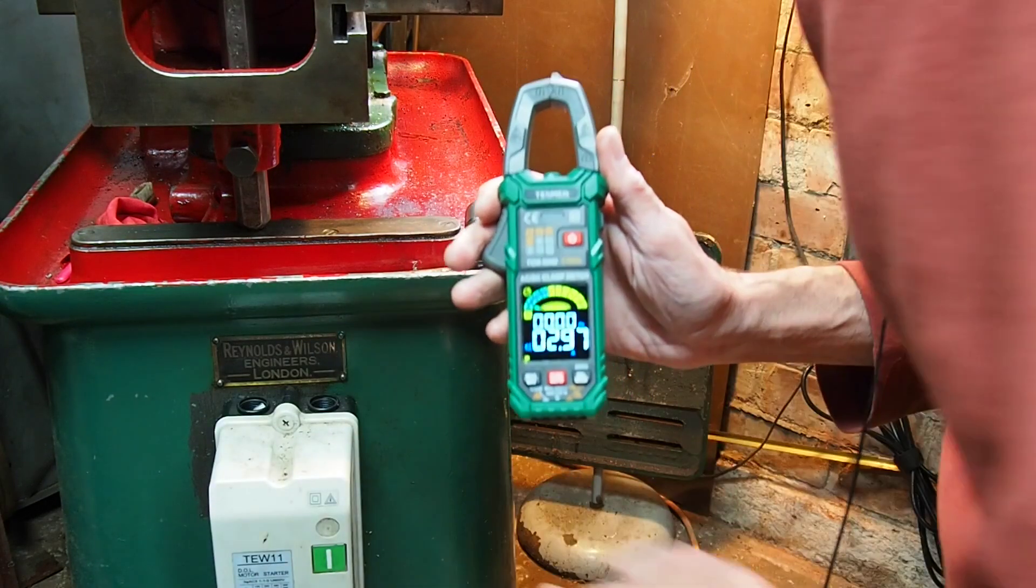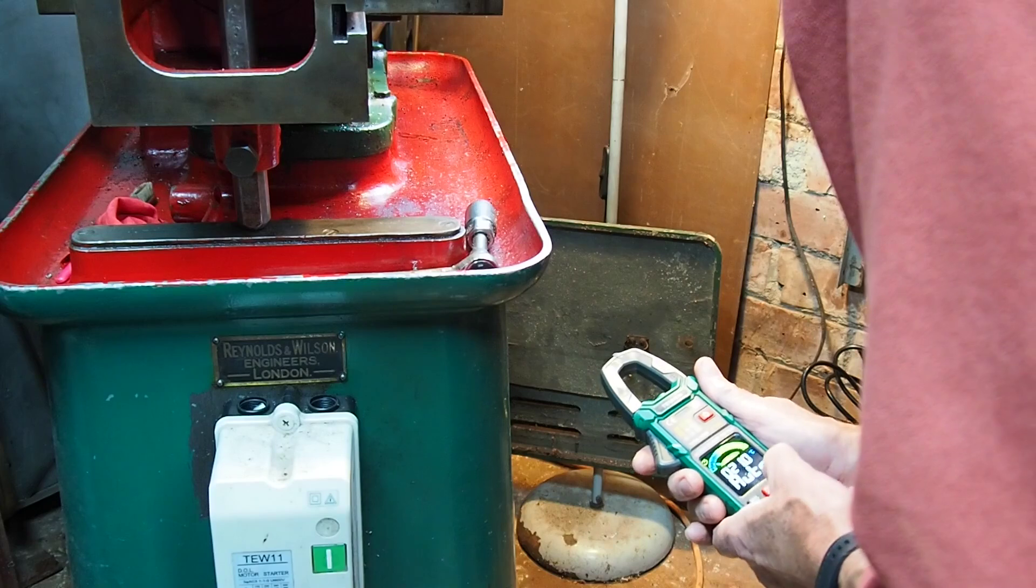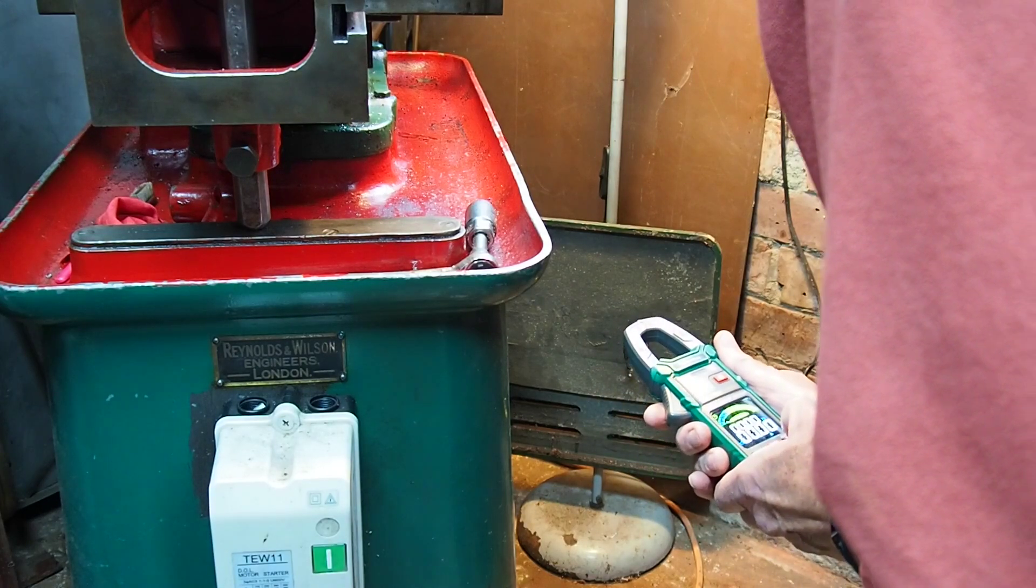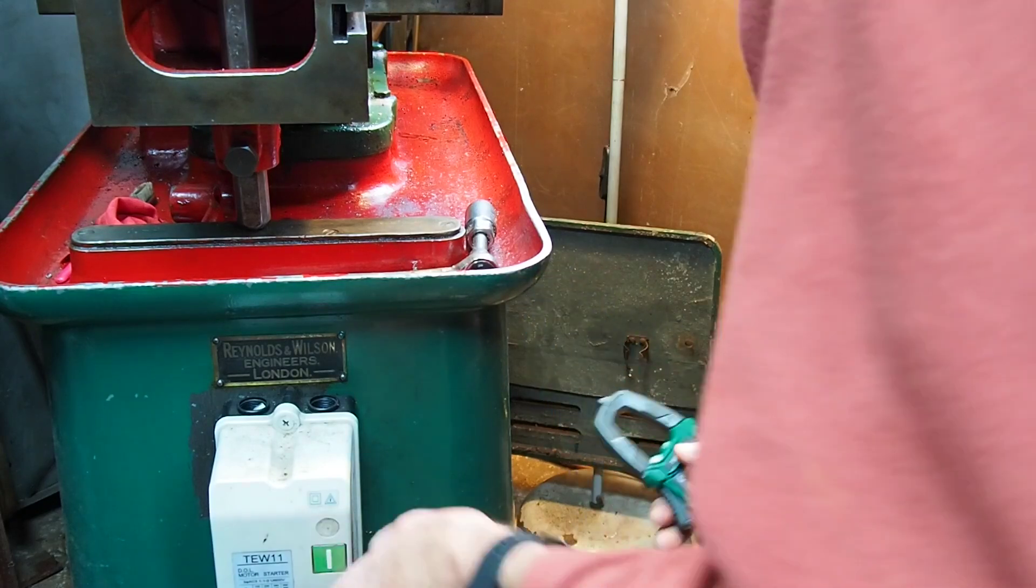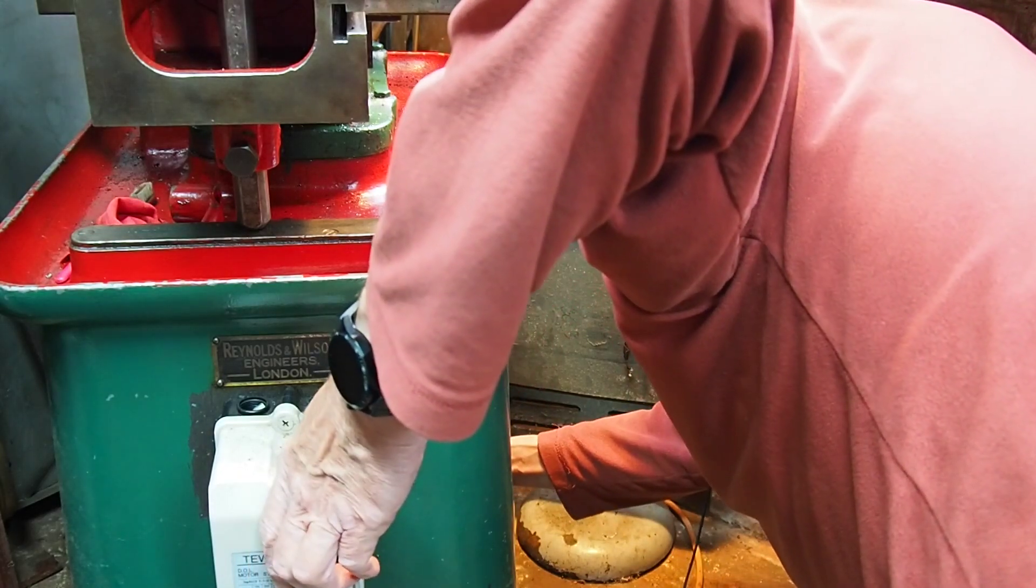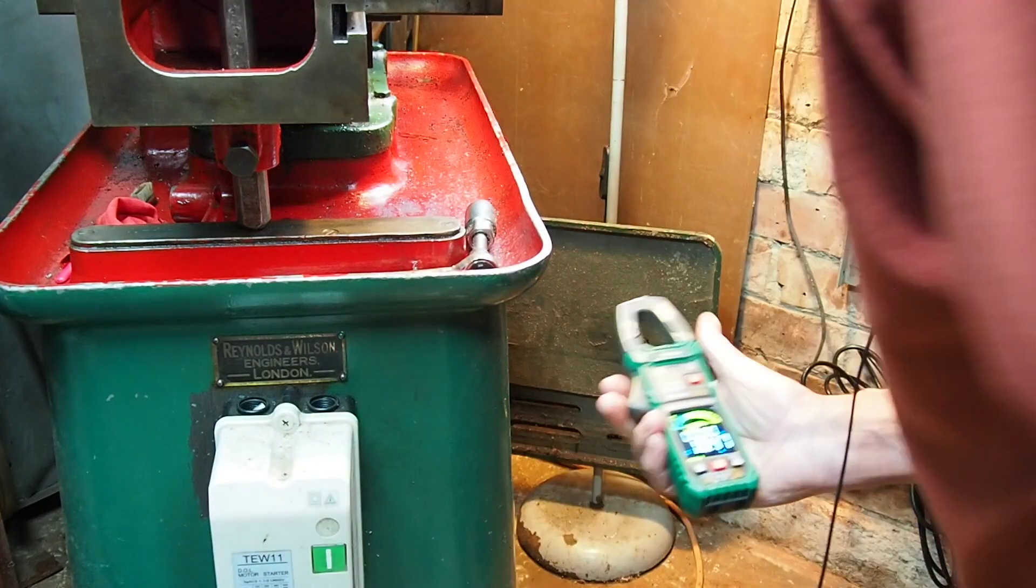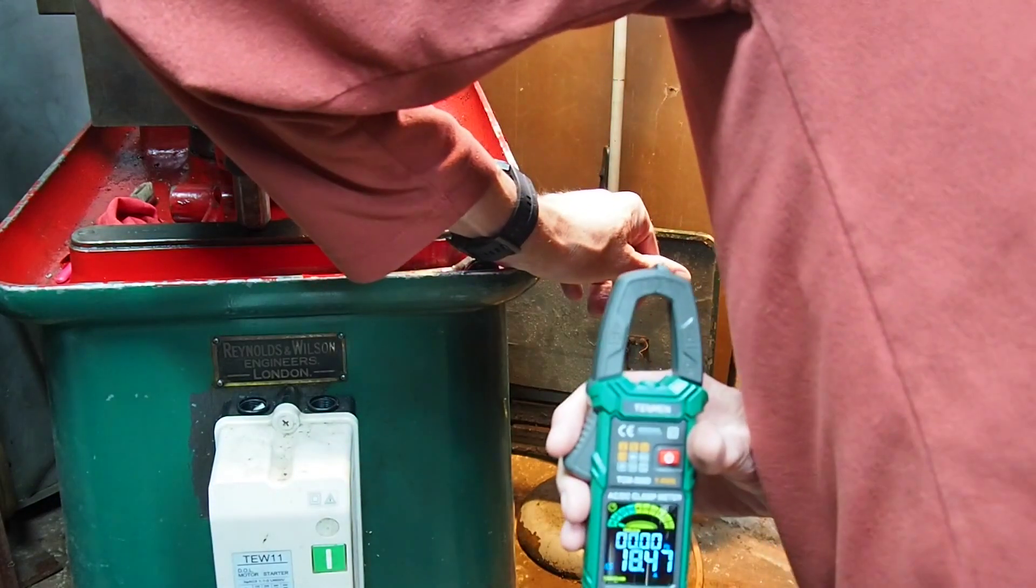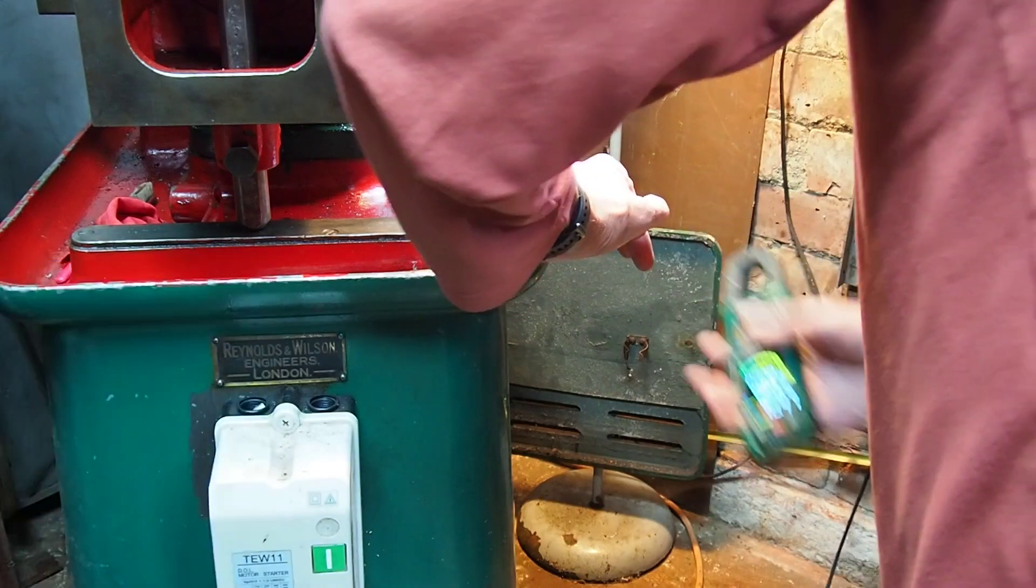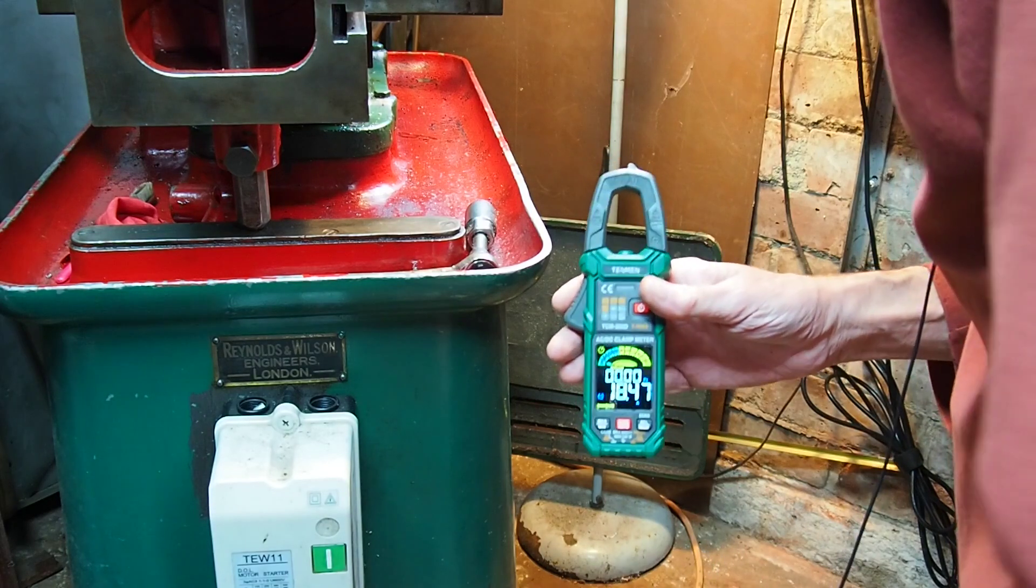Now I'm going to try measuring the inrush current. I've never done this before so I'll be interested to see how it works. We're in amps, we need to select inrush, like so. Then we need to put the meter onto the wire and start the motor. I'll stop it again because we've got a reading. There you go. Briefly it reached 18 amps when it was starting up. That's quite a considerable amount of current before the motor settles down. That's AC current and inrush measurement.